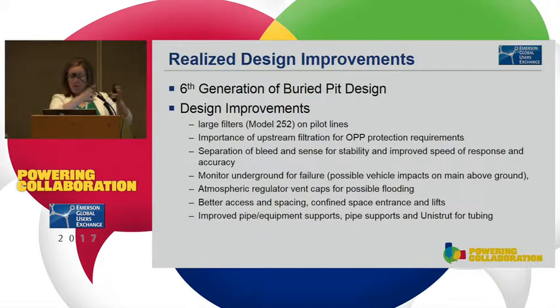The healthier we keep that station and equipment, the better off both the regulating and overpressure protection equipment are. A big improvement for stability was separating out the sense and bleed lines. This allows the station to go in almost anywhere, and because they're both in stable spots and not interfering with each other, you get rock solid operation all the time. Some stations will work when you bring the bleed and sense together, but every once in a while you'll hit stations where they hit system harmonics, the gain's too high, it responds too quickly and goes unstable, and technicians will never figure out why it works at three stations and not this one.